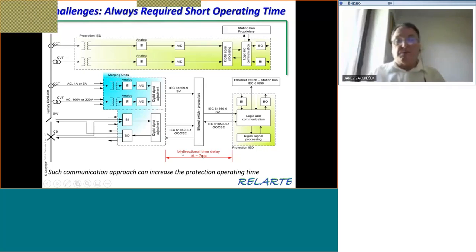So if you look into the required communication time and process times in between, the maximum times can reach practically 6 to 7 milliseconds of time delay in the fault clearing time. So we have, for example, today modern traveling wave protection. The fault is detected as a traveling wave itself in, let's say, 200 microseconds, then maybe some communication links and so on, but we come to at most some 3-4 milliseconds if communication is good, and we can operate in such time. But if we add everything here, we come to even more, 10 or 15 milliseconds. Why should we do this?